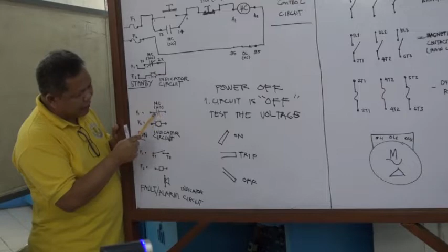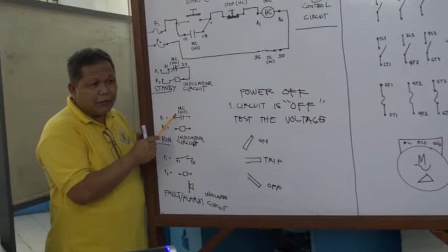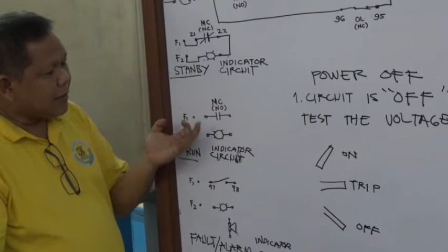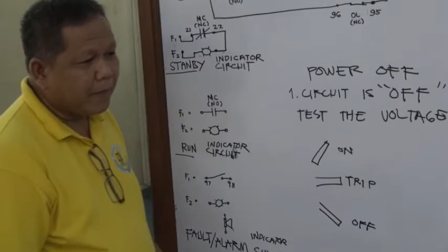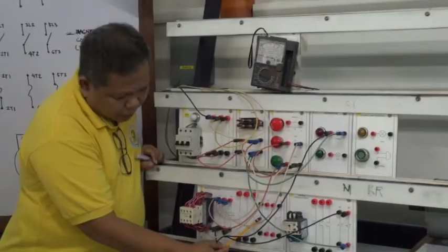Take note of the symbols - normally open. So magnetic contactor, normally open. What we are going to do is locate on the magnetic contactor where the normally open terminal is. We can't use the main contact here - we go to our auxiliary contact. This one is normally open.